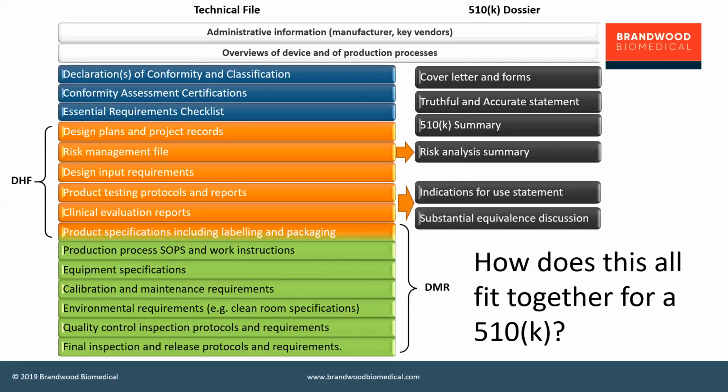Then you also have your indications for use statement and your substantial equivalence discussion. Those are things that are taken from the majority of your design inputs, your verification and validation activities. So your CER will be a huge part of what you end up putting into your substantial equivalence discussion.